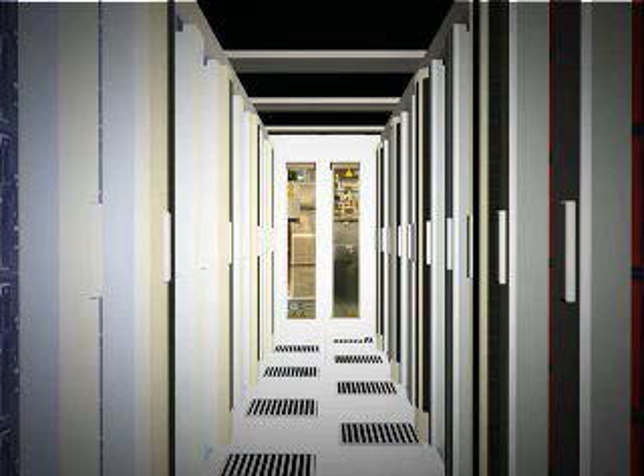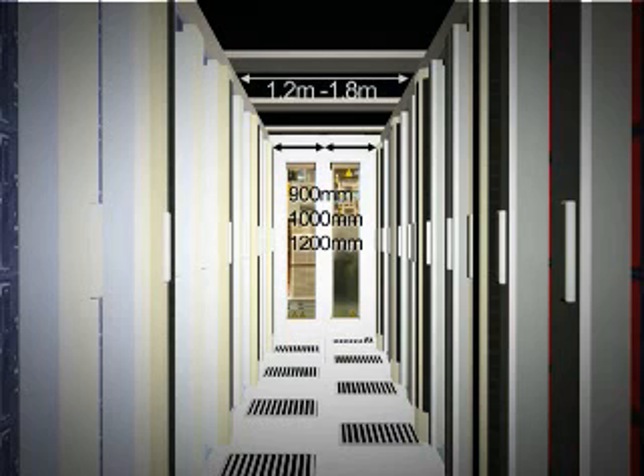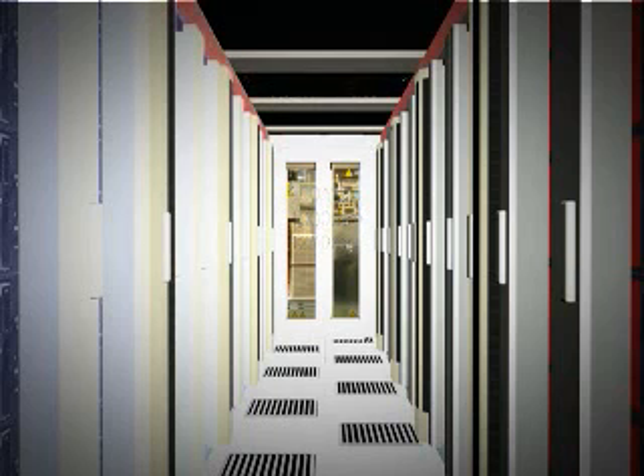Rittal's Cold Aisle Containment system has been designed to be adaptable. The doors at the end of each aisle will fit 900, 1000 and 1200 mm deep enclosures. The roof panels also allow us to adjust the width of the aisle from 1.2 meters to 1.8 meters. The inclusion of a 100mm plenum, which increases the roof height, not only allows us to provide additional headroom, but provides important space for additional features such as security webcams and fire extinguisher systems.